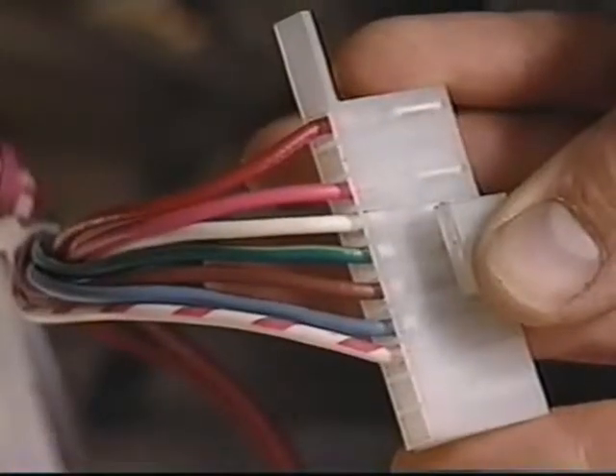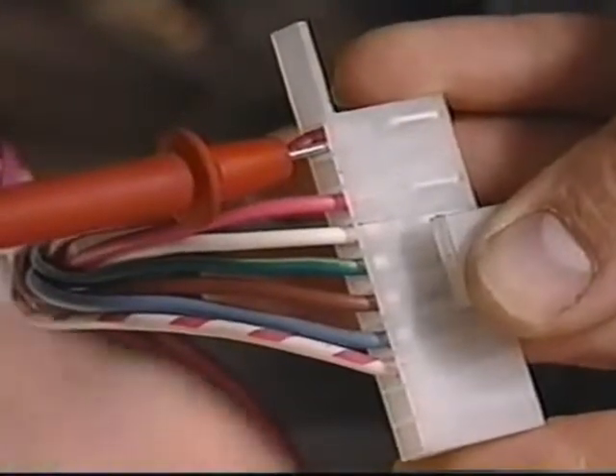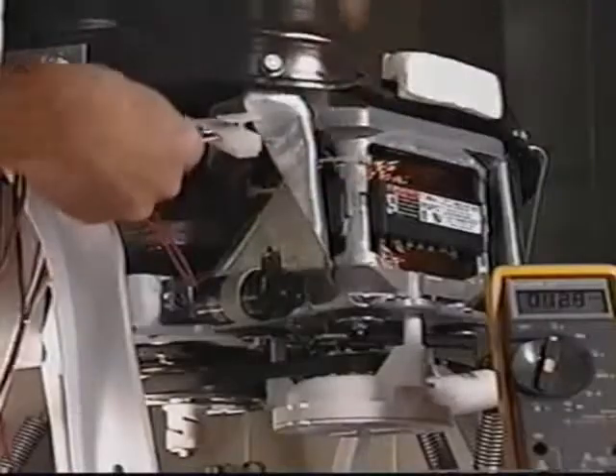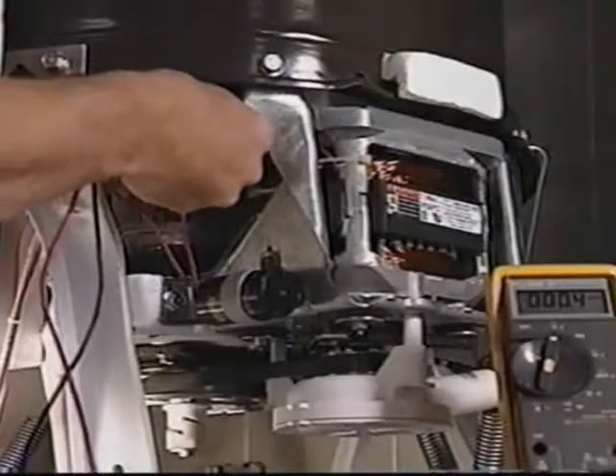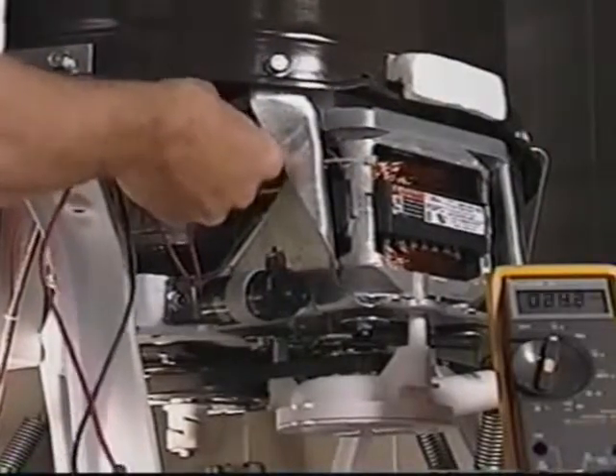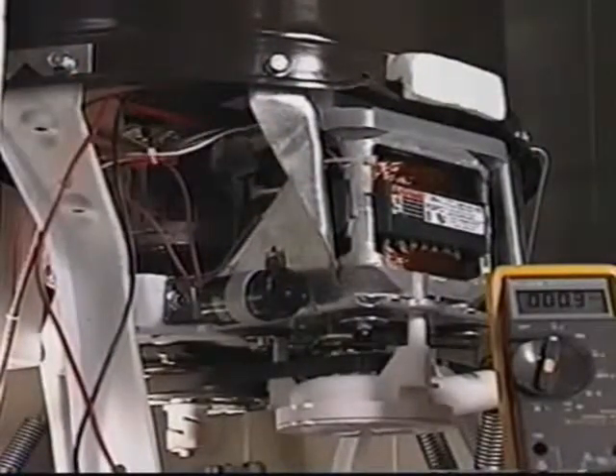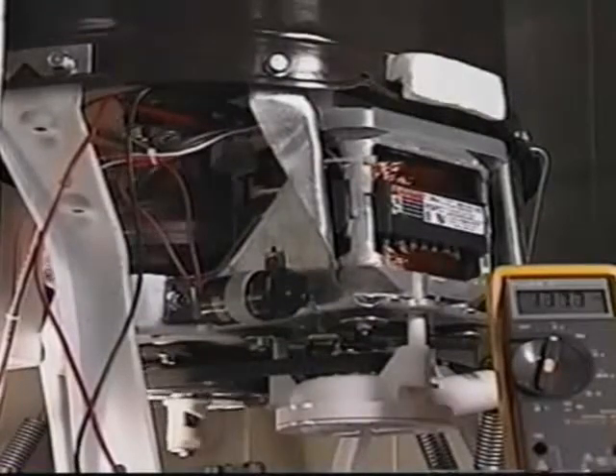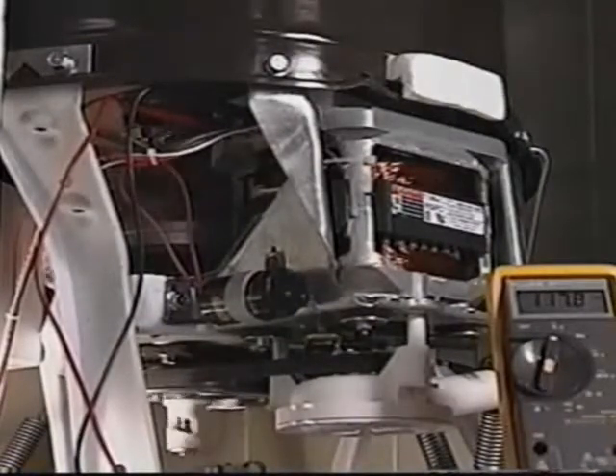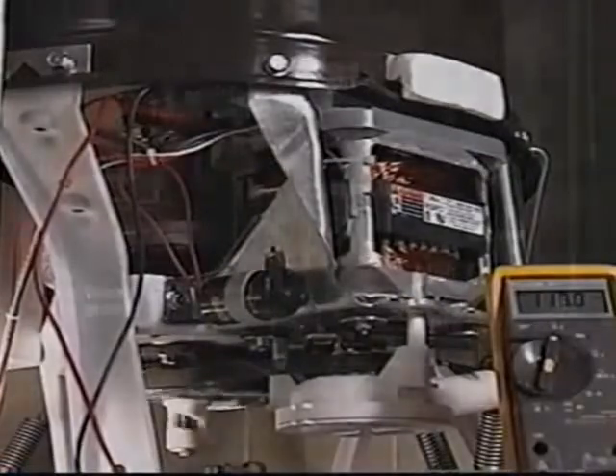In agitate, a red wire, pin number 1, provides line 1 voltage to the start winding. A brown wire, pin number 6, provides neutral to the start winding. With voltage across both windings, the motor should start and run. The centrifugal switch opens and removes the start winding circuit once motor RPM is achieved.